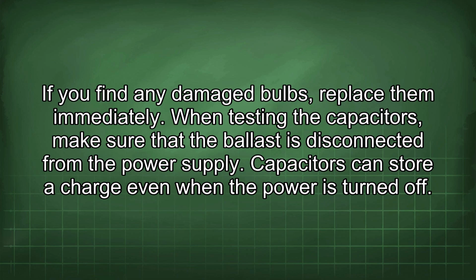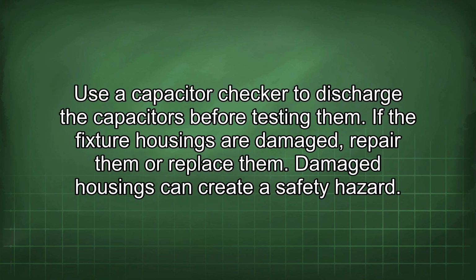When testing the capacitors, make sure that the ballast is disconnected from the power supply. Capacitors can store a charge even when the power is turned off. Use a capacitor checker to discharge the capacitors before testing them. If the fixture housings are damaged, repair them or replace them. Damaged housings can create a safety hazard.